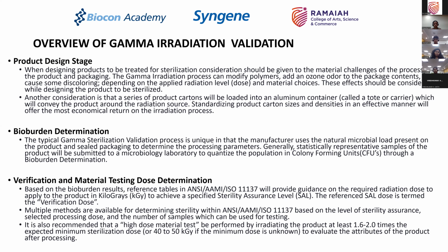It is also recommended that a high dose material test be performed by irradiating products at least 1.6 to 2 times the expected minimum sterilization dose, or 40 to 50 kilograys if the minimum dose is unknown, to evaluate the attributes of the product after processing. So you also do a high radiation dose test, meaning that, remember we spoke about 25 being the standard dose, and this comes from the ISO 11137 guidelines. So you also do a high dose material test, to see what happens if I expose it to 1.6 to 2 times that dose.